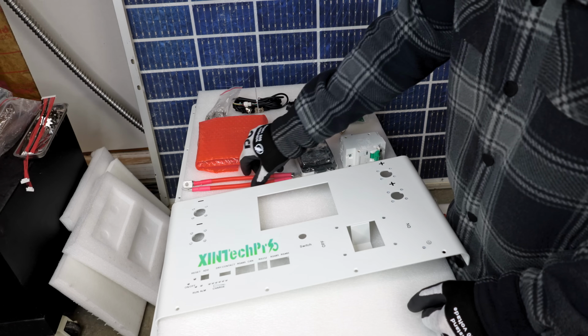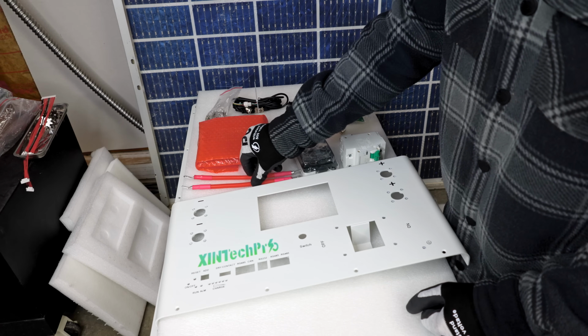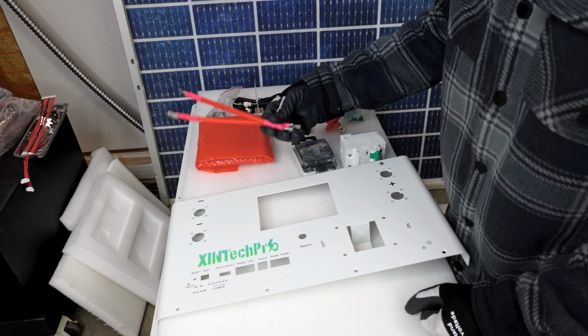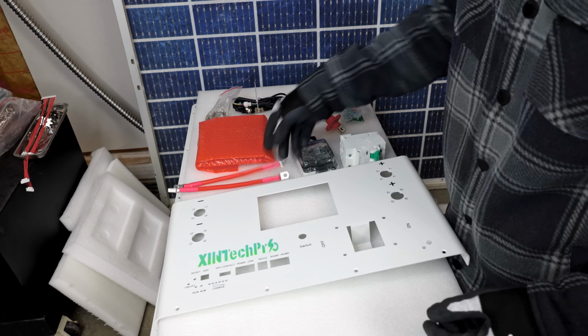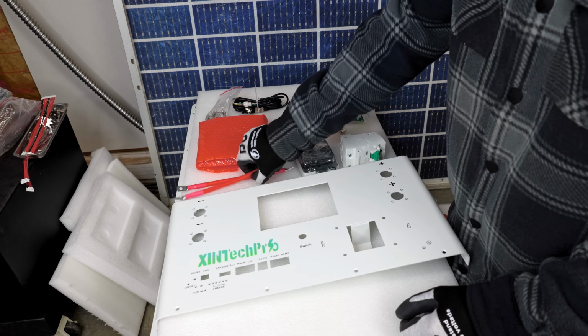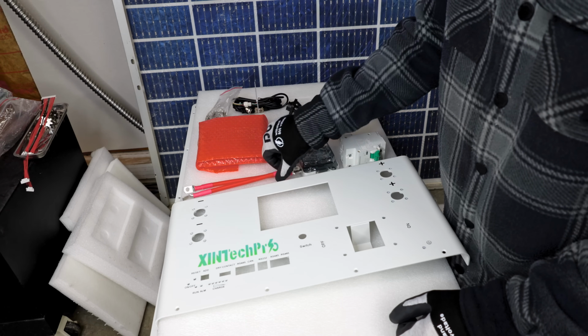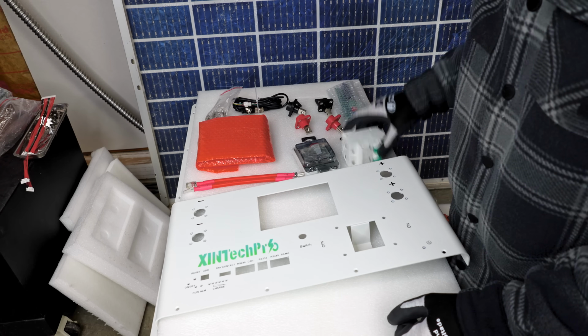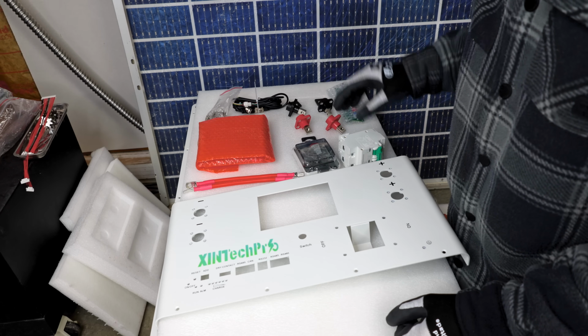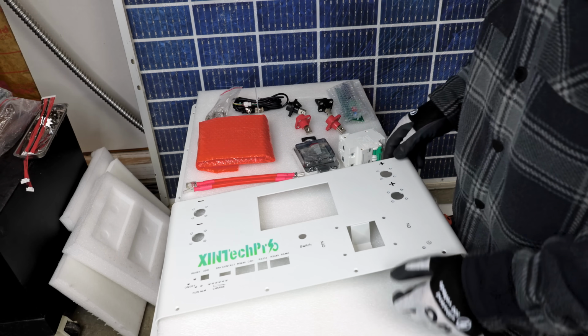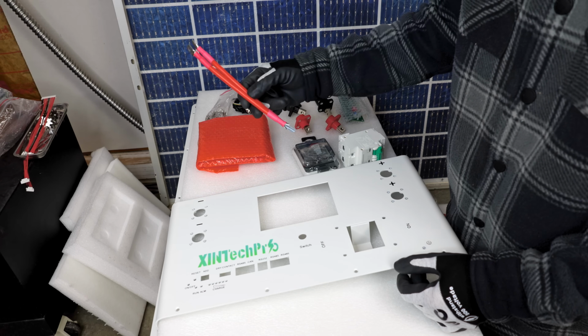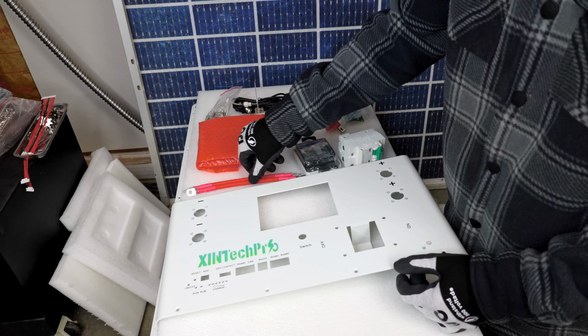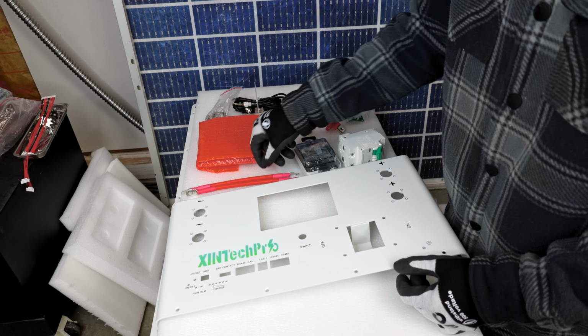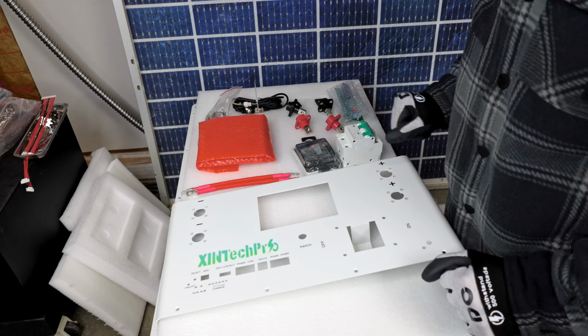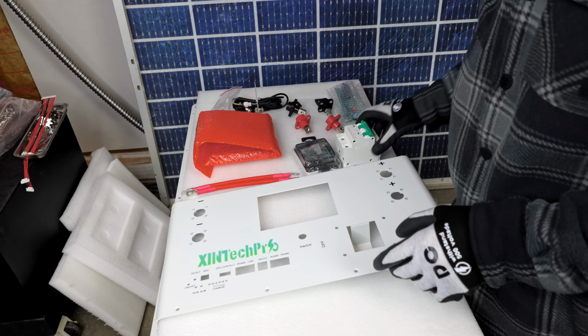I would like to see the equivalent of a 2-aught cable, and this isn't going to do it. If these were 4-gauge, I guess it would be okay, but 6 is definitely not enough. The countermeasure will be to change the BMS setting to 100 amp instead of 200 amp, and the breaker really should be limited to 100 amps at that point. But what I'll actually do is go back and change out these cables to a lower gauge number—a thicker cable. For now, for assembly instructions, we'll just go ahead and put it together.